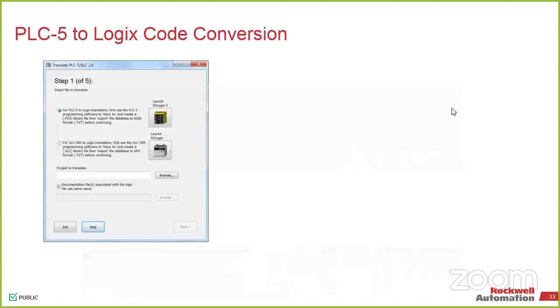So I think the largest install that we've done is plus 50 units around the area. Overall, we've probably done 400 to 500 different installs with this system. And it's always a 50-50. It either makes sense to do the conversion because everything's kind of the way it is, they have enough space, and they're doing it as a phased approach. But if you don't have the wiring drawings, if you haven't touched the system in years, and none of the code has been optimized, in most cases it's probably worth just doing a redo.